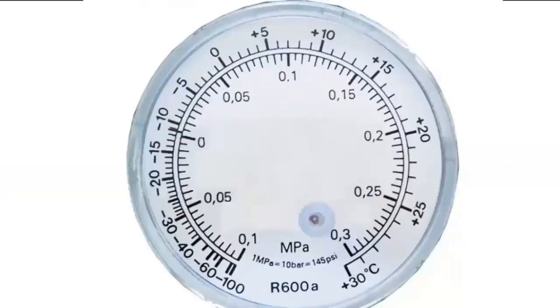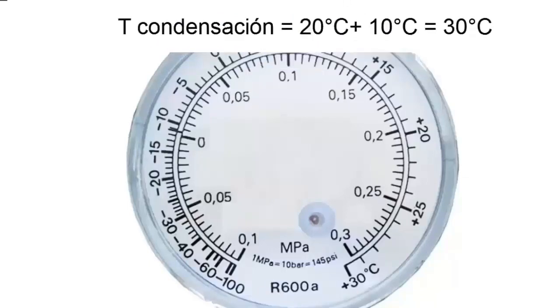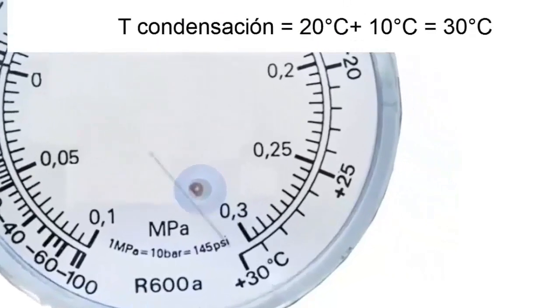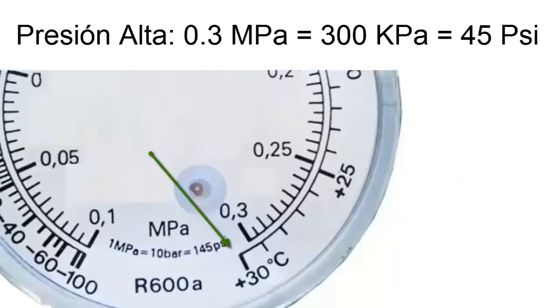Now we are going to verify what will be the value of the high pressure. For an environment of 20 degrees Celsius, we are going to have an average condensing temperature of about 30 degrees Celsius. Now let's set the needle to 30 degrees Celsius and note the pressure value.